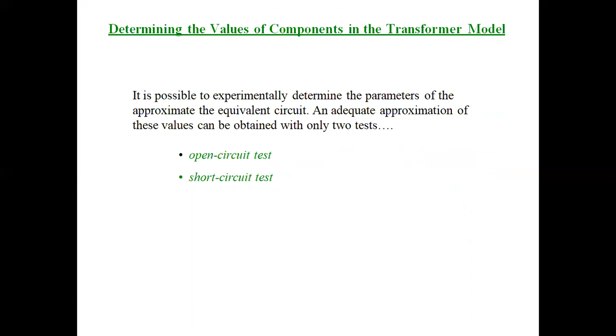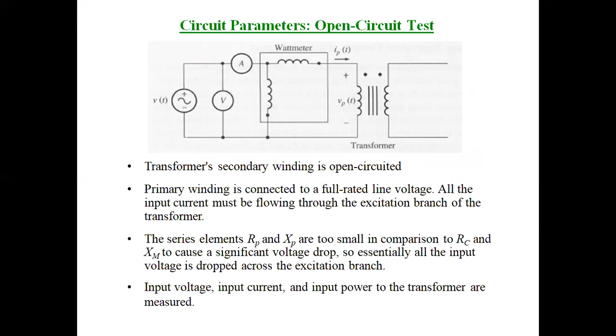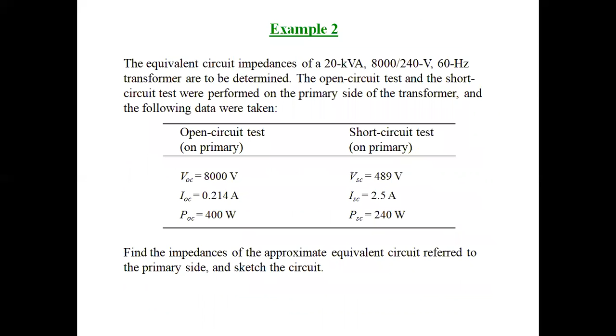To find the losses, we are going to conduct two tests on our transformer: the open circuit test and the short circuit test. From the open circuit test, we can find our core losses. From the short circuit test, we can find our total copper losses. Once the losses are known, we can find our efficiency. The transformer efficiency is output power divided by input power, that is, output divided by output plus losses, otherwise input minus losses divided by input.